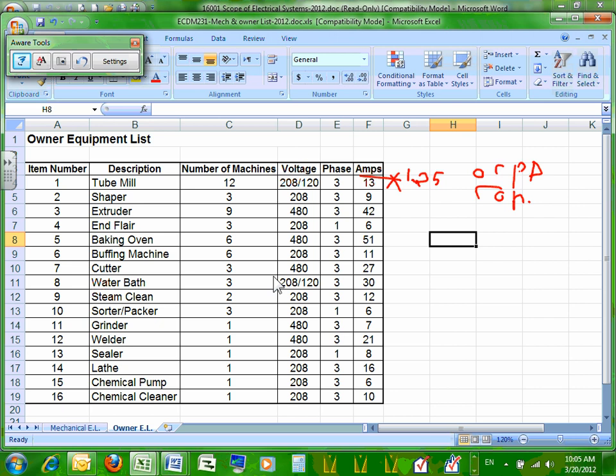And when we do 120, I was assuming we're giving it a neutral here, that machine? Yes. So I would be looking at a drop that has a receptacle that has a neutral in it. So it's probably a 5-wire drop if we got, well, that's a single phase. No, it's 3-phase. So it's probably a 5-wire drop: 3 phases, neutral, ground to a receptacle that'll accommodate the 5-wire with that amperage configuration.